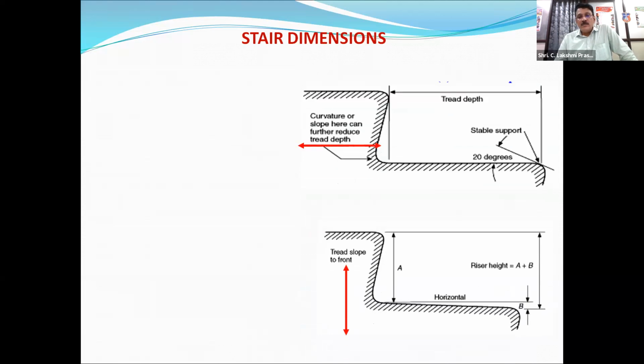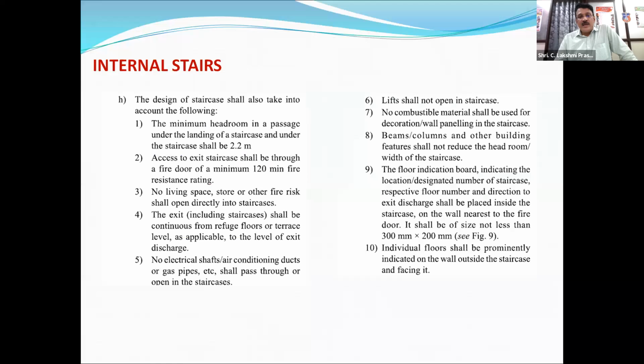Tread risers. For internal stairs, they have given many prescriptions. No electrical shaft, air conditioning ducts or gas pipes shall pass through or open into the staircases, and even a staircase around the lift is not permissible, because the lift well will act as a chimney for spreading the smoke. If the lift shaft is not properly pressurized and protected, it will spread the smoke to all the floors, and the staircases in turn will be filled with smoke. People will not be able to use them. So a staircase around the lift is not permissible as per the code.